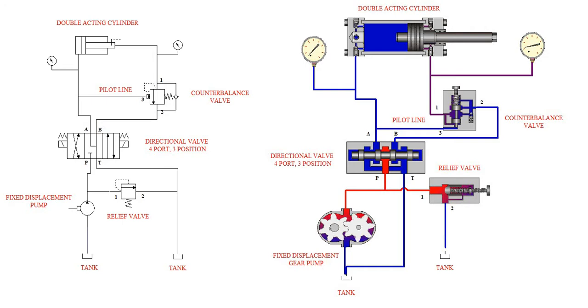Okay, so hopefully that gave you a good idea of how it all works, but now let's look at it in detail. So when we start here, what we see is we've got a spool that's in the center position, pressure is blocked right here, and we see our relief valve is open, right? Our relief valve here, the poppet's off the land, allowing a flow path from 1 to 2.